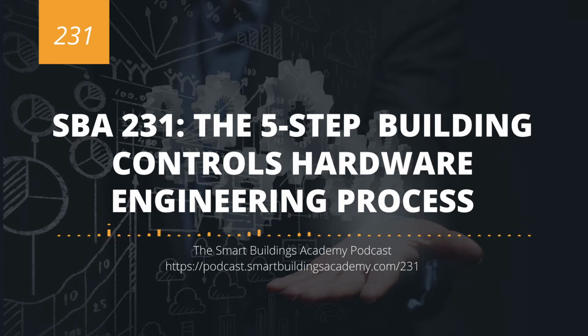And I know this is a little crossing into software engineering, but there's a little software engineering in all hardware engineering. But I'm going to look at that and say, okay, do I do a separate controller so I have standalone for that fan coil? What is that fan coil serving? And then I make a decision, standalone controller, or do I use the chiller controller? It's different choices based on cost, based on system type, building type.